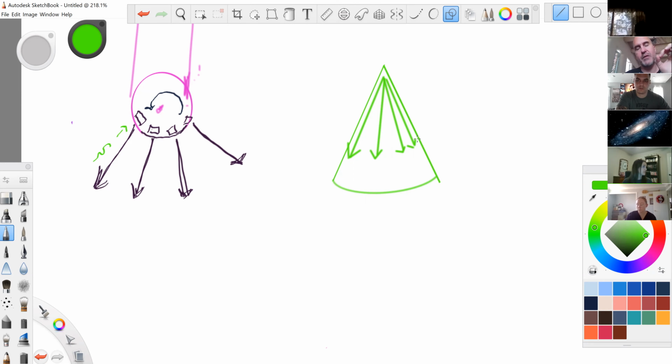They know exactly the speed of rotation of the entire mechanical transducer, they know exactly the RPMs, and so they're timing it so that this is the first one, second, third, fourth, and then they start back to first, second, third, fourth, and basically you get 1, 2, 3, 4 beams here. Once again, obviously it's going to be more like 50, 100, 200 beams.